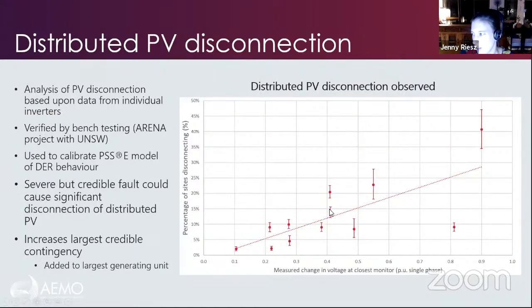So on disconnection behaviour, this chart is showing you measurements from power system disturbances from faults that we've seen in our network. When we have a fault, it causes a voltage depression in a section of the grid. And we found that that causes a percentage of the distributed PV systems to disconnect from the system. And the amount of them that will disconnect, the proportion of disconnections, is a function of how severe the fault is. So for the most severe faults that we've seen, we could see up to around 40% of the distributed PV in a region disconnecting. And we verified this, investigated it further with laboratory bench testing of a large number of inverters that are installed in our grid to confirm that this is a response to that voltage depression.